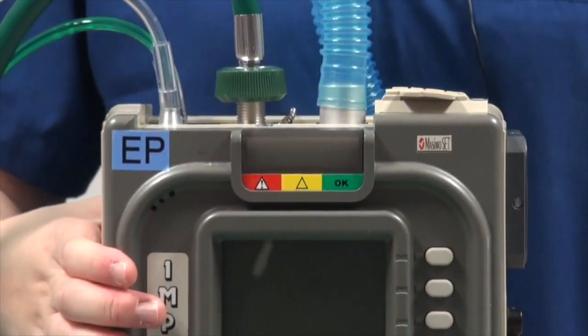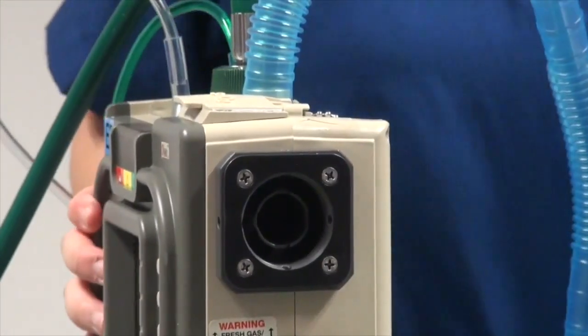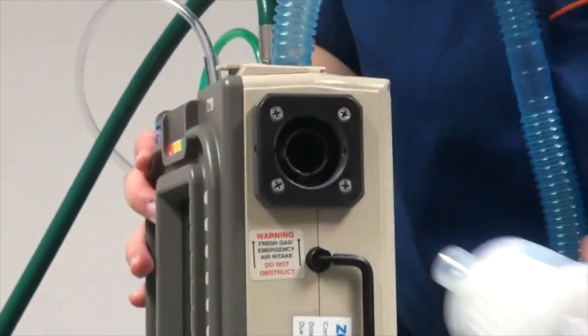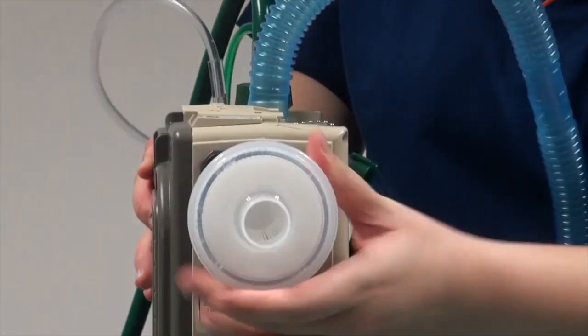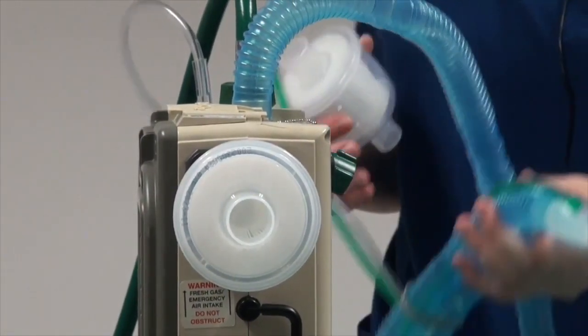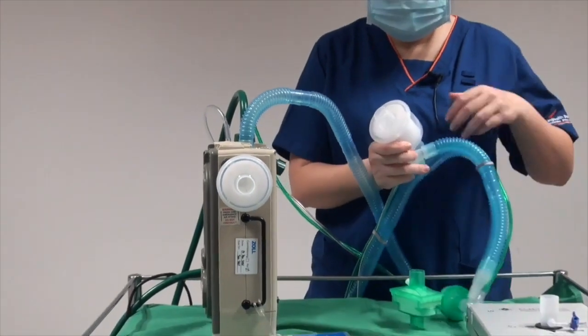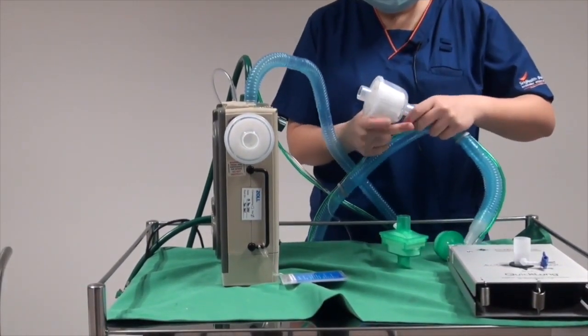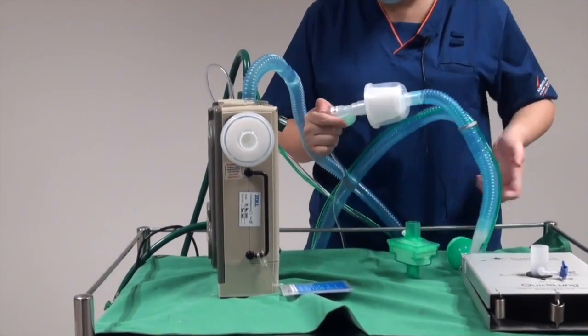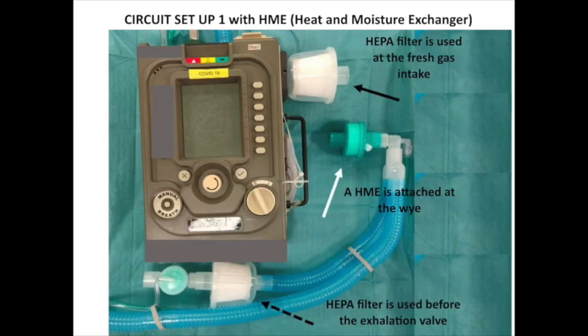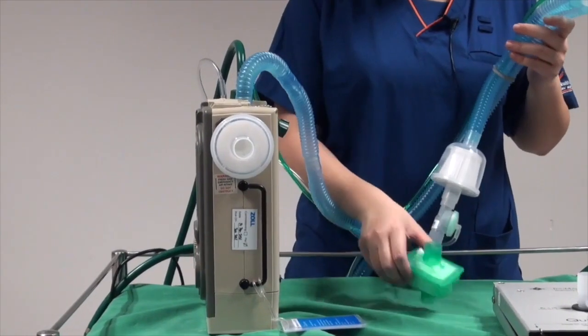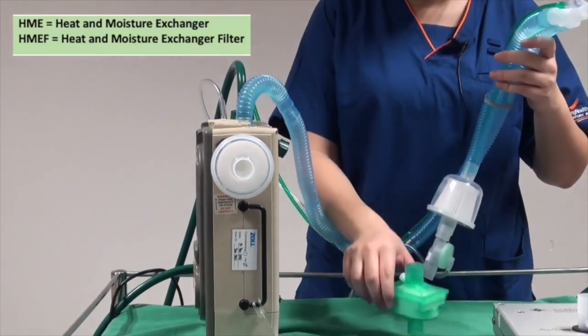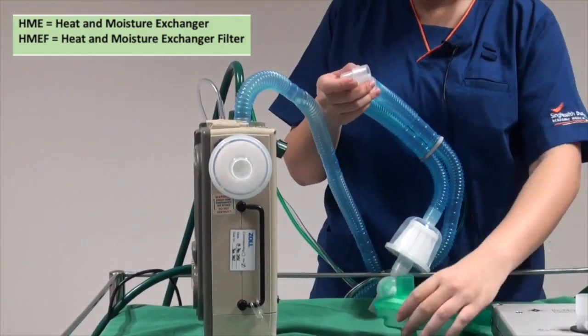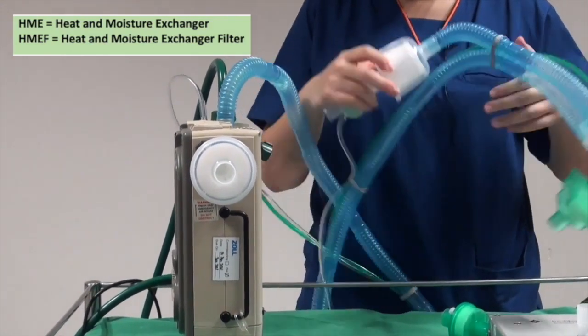If you are using this ventilator on a COVID-19 patient, put a HEPA filter on the fresh gas intake. The other HEPA filter goes before our exhalation valve. Make sure your connections are secure. If you are using a HMEF in your institution, you do not need a HEPA filter here.